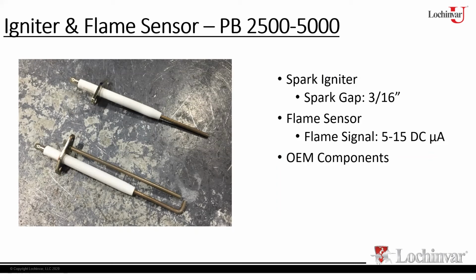Now, sometimes people replace them just because of their maintenance schedule. I have seen guys replace the igniters and the flame rods every year. That's just a yearly thing they change out before every heating season. If you want to do that, that's perfectly fine. I've got no qualms about that at all. If you do that, that's great. But it's not necessarily needed, right?